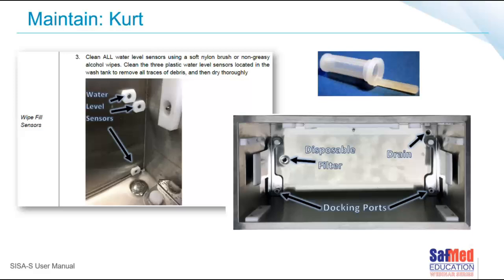Okay, so on the example that we have on the screen, there are 3 water level sensors that you see on the left side picture. Starting with the one right at the bottom, that level sensor will pick up if there's still water in the ultrasonic bath. The middle sensor is the fill sensor, and that sensor will stop the inlet water valves for water entering the ultrasonic cleaner to say the ultrasonic cleaner is at its optimal level and it's ready for the cycle. And the third sensor right on top is the overflow sensor. So not all models have overflow, so it varies from unit to unit.